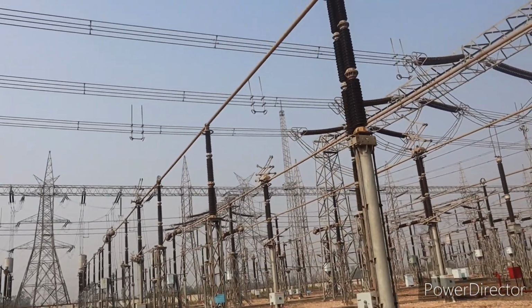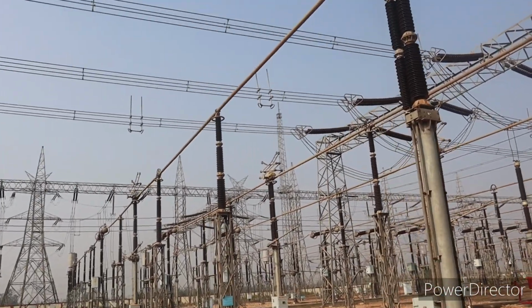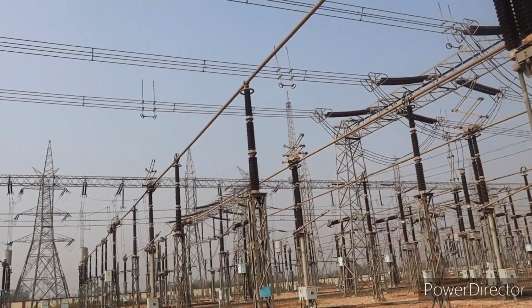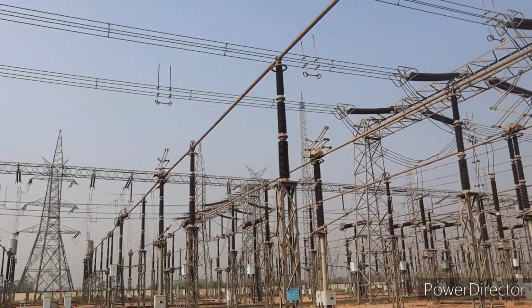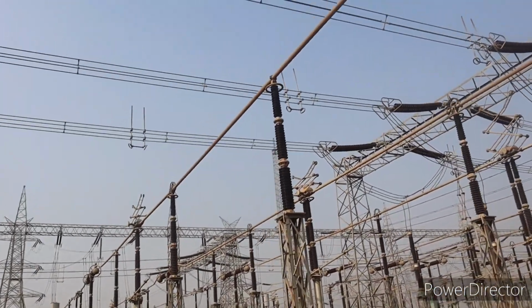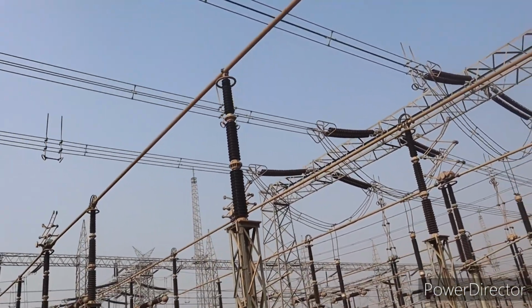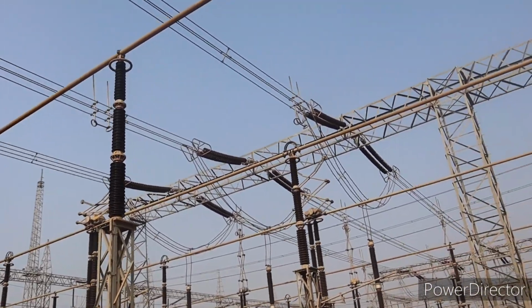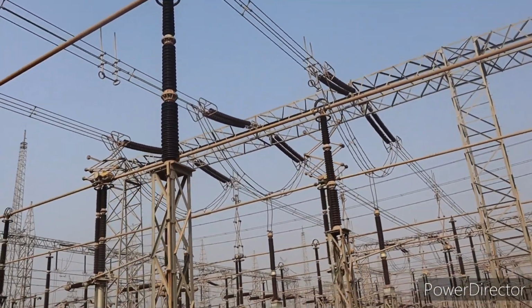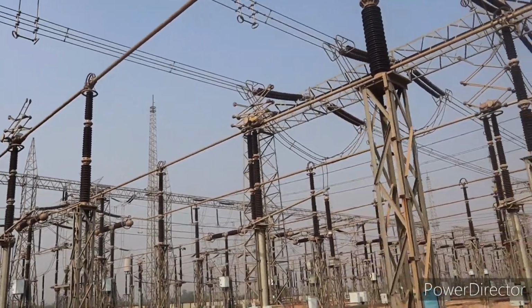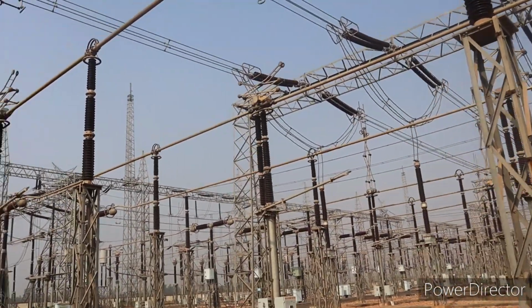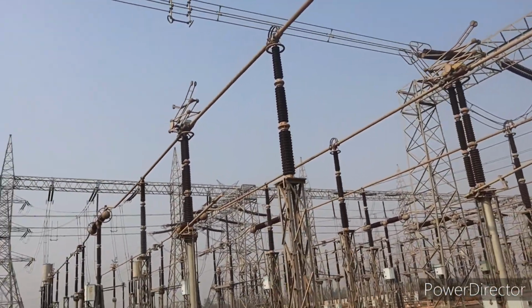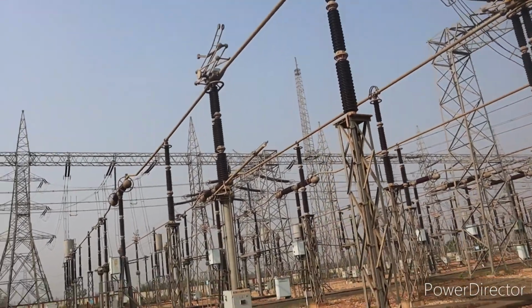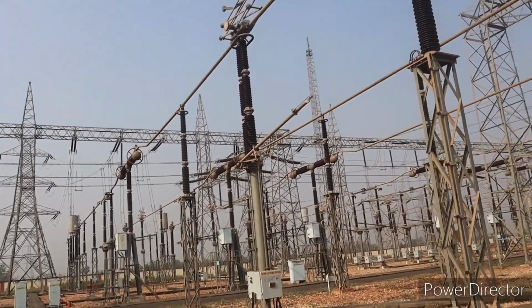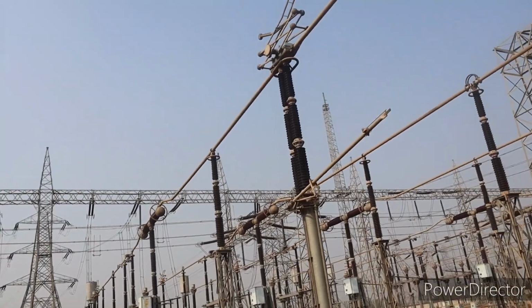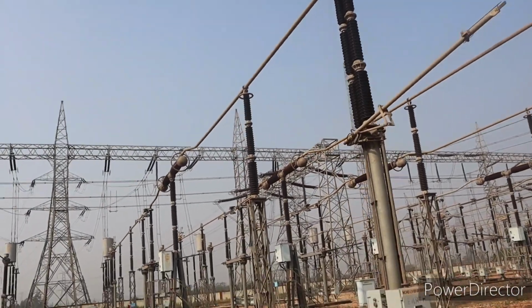This is main bus 2. All isolators of main bus 2, that's main 89B, are now in open position. The lines feed from main bus 1. It is a pantograph type isolator. Main bus 2 and bus side outer isolators are arranged in this isolator.